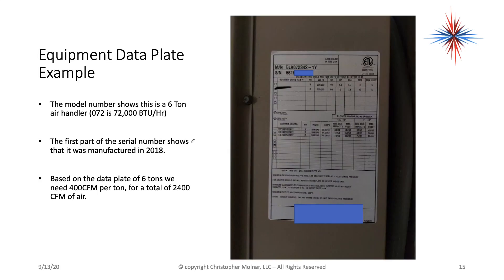Here's an example of an equipment data plate — the serial number is blocked out for privacy. The model number shows this is a 6-ton air handler; '072' tells me it's 72,000 BTU per hour, divide by 12 and it's a 6-ton unit. The serial number indicates it was manufactured in 2018, so it's a relatively new piece of equipment. Based on 6 tons, I need 400 CFM per ton for a total of 2,400 CFM of air.